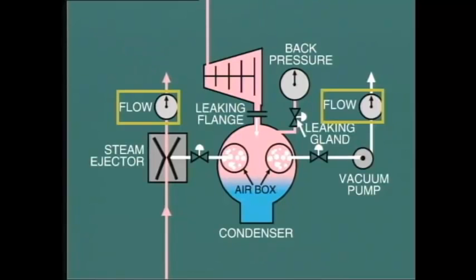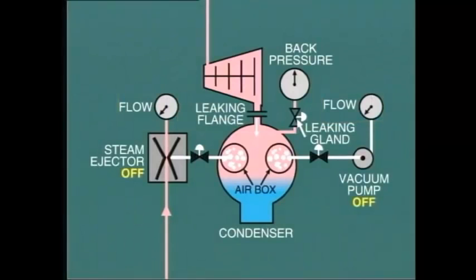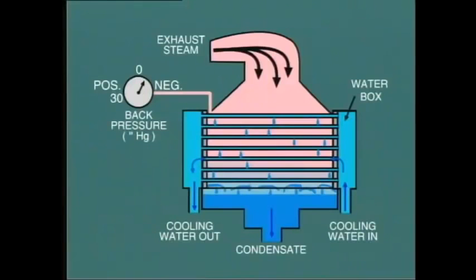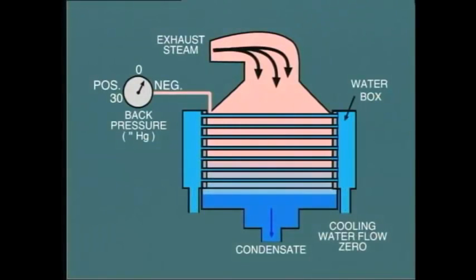In fact, a good test of this during operation is to shut down the vacuum pump or steam ejector and observe the rate at which the back pressure increases. This should be quite slow, say 1 inch of mercury in about 30 minutes. Compare this with the change which would take place if all of the circulating water flow were to cease, perhaps due to a trip of the circulating water pumps. In this case, with no condensing taking place at all, the back pressure would rise immediately, and the turbine would have to be tripped. In practice, this takes place automatically. And we'll be discussing this when we look at protection devices in the next module.